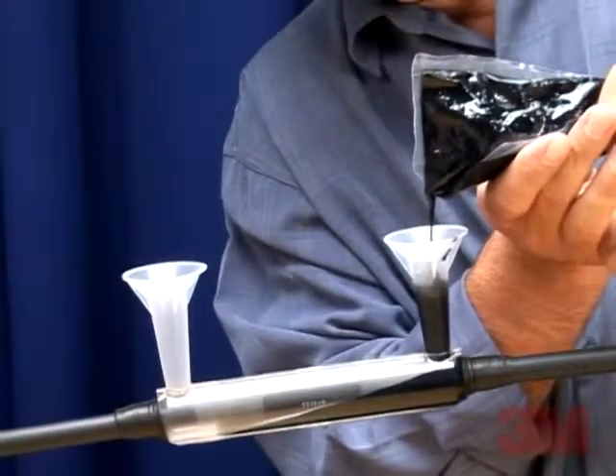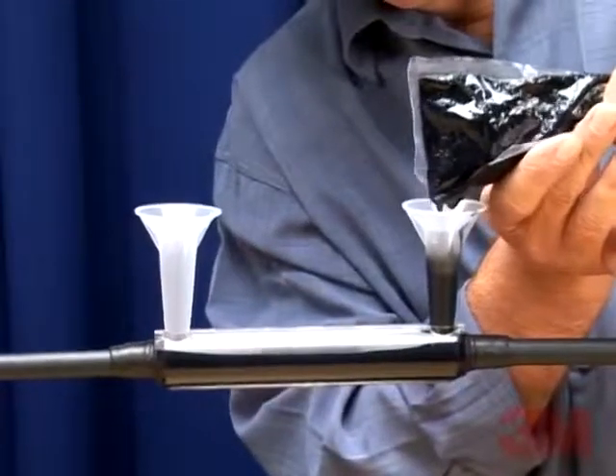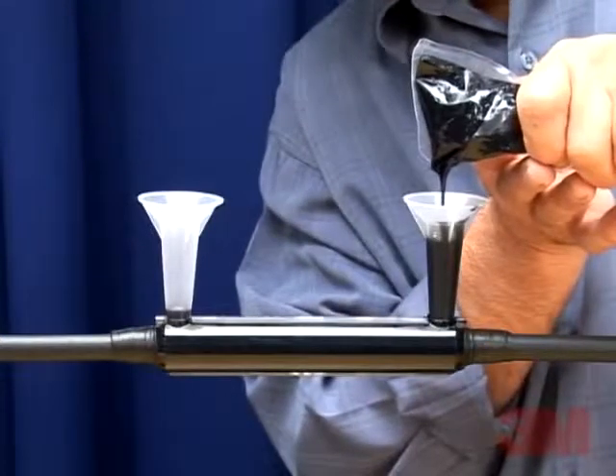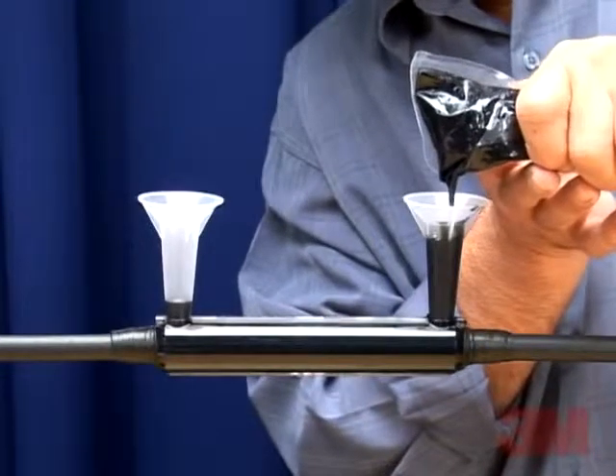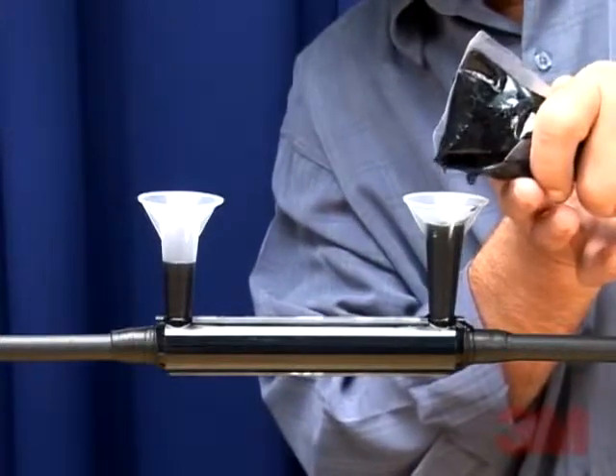A helpful hint: tilt the splice slightly and pour resin in the downhill side spout if area permits. This will push the resin to the raised end spout, pushing excess air from the splice. Splice cure time is 1.5 hours and is submersible in 4 hours. Clip off the spouts if desired. Your 82A1 power cable splice is now complete.